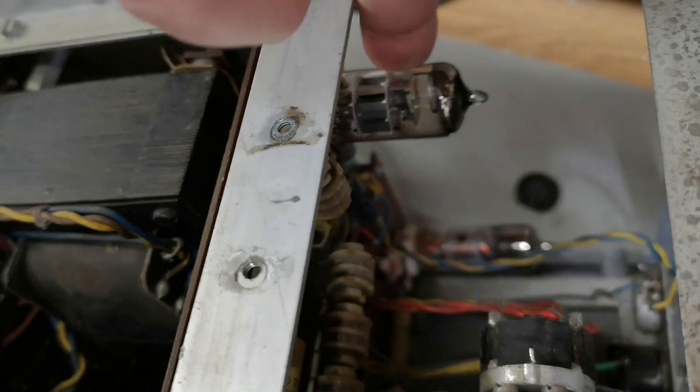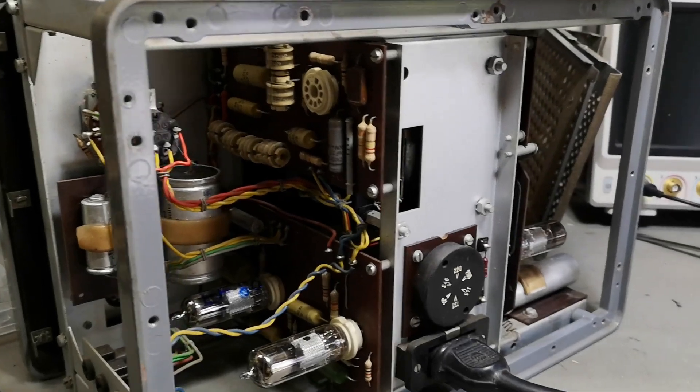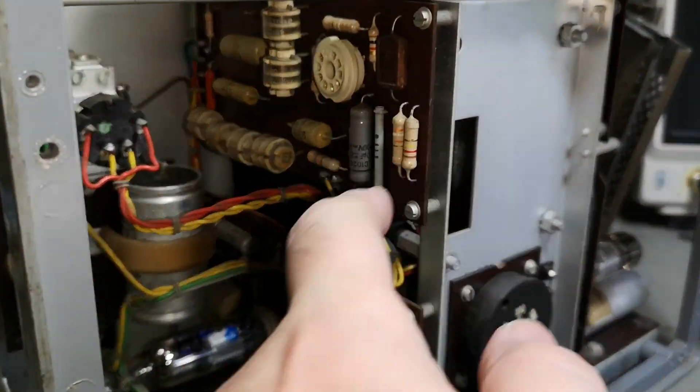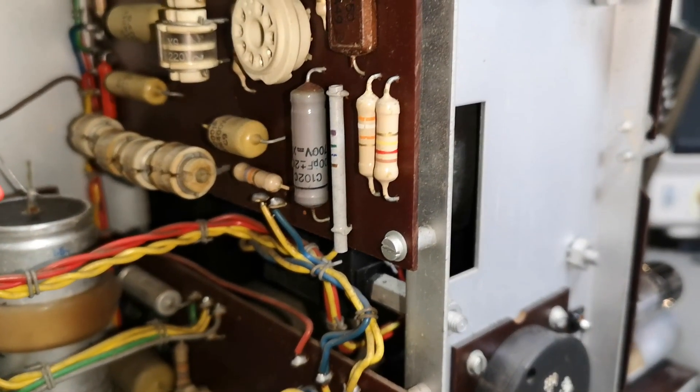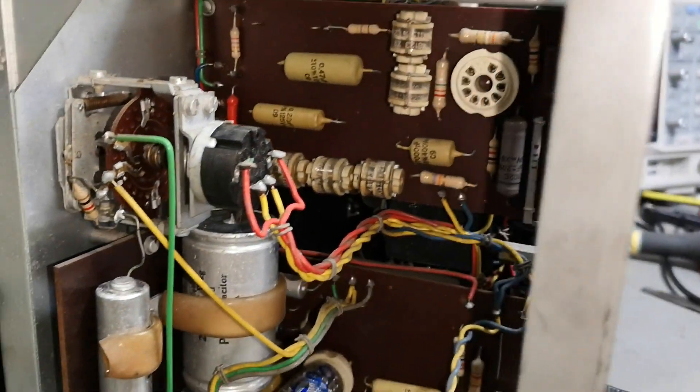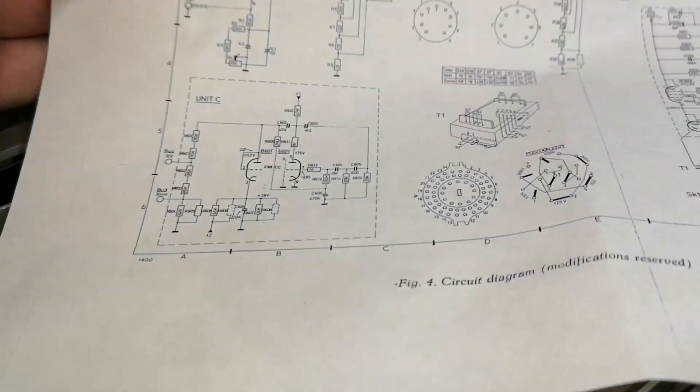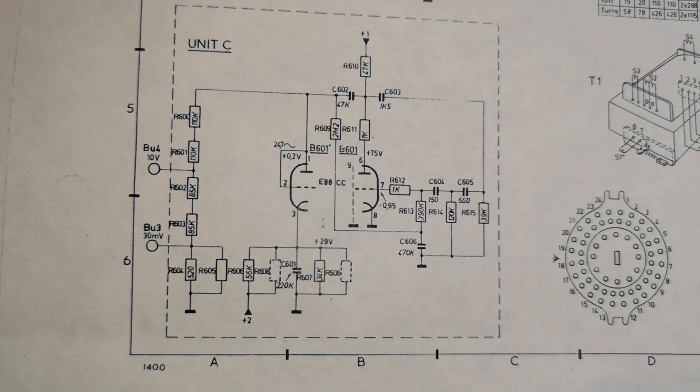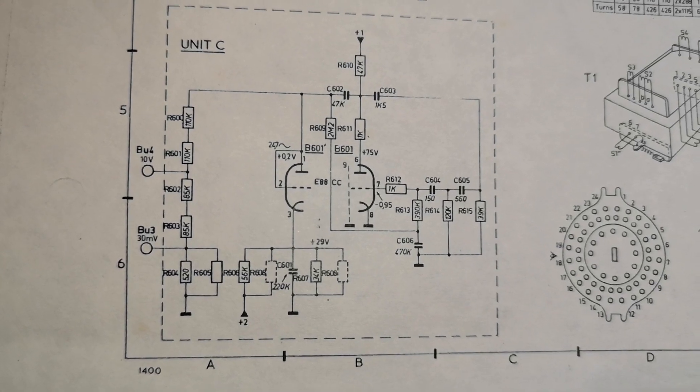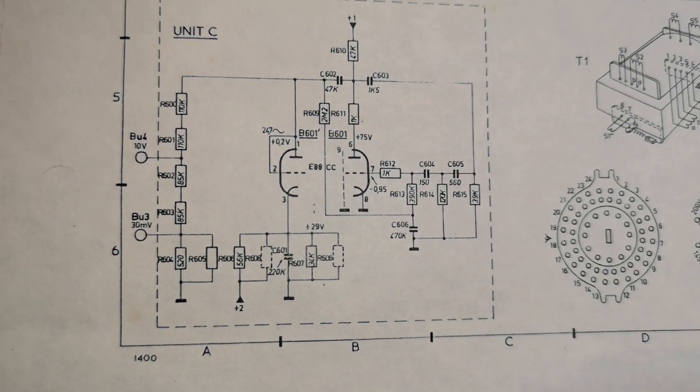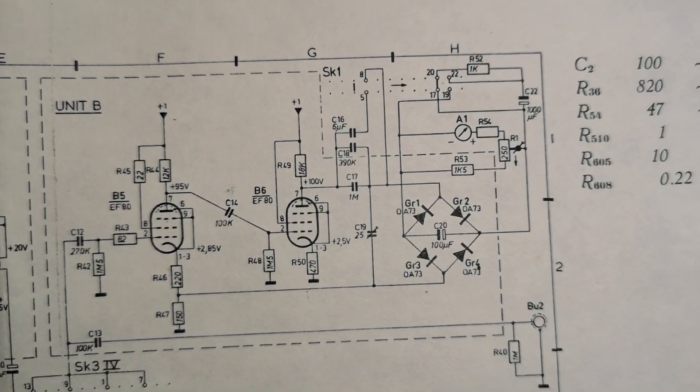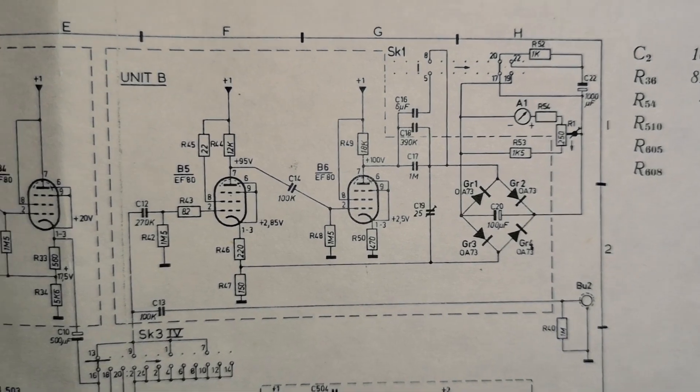I think I found it. It is that easy sometimes. Let's see if I can find a new one. Oh, that is actually classic. This whole unit here is what they call unit C. This is only an oscillator used for calibrations, and we got two outputs here from this oscillator. So we really don't need this oscillator at all.